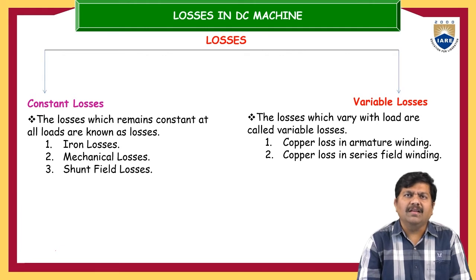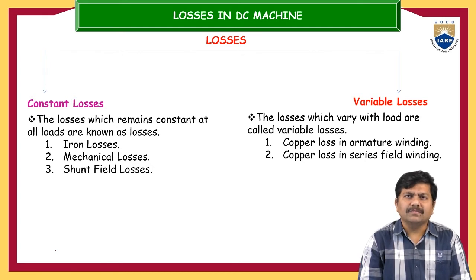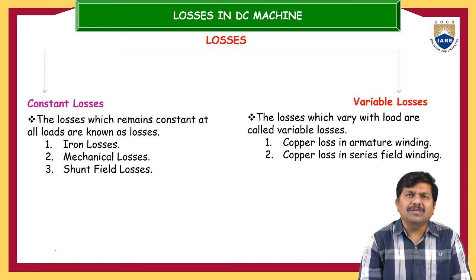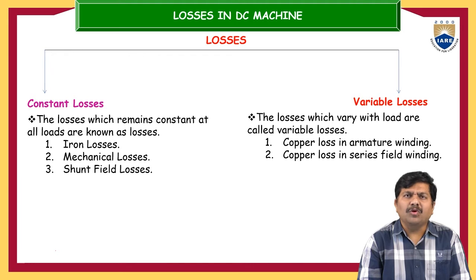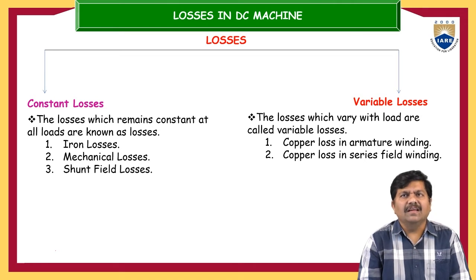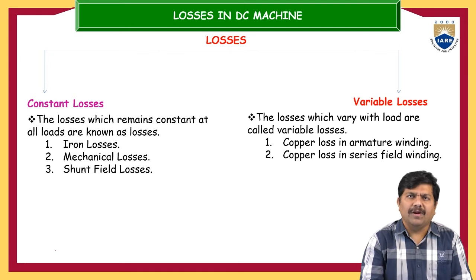Examples of constant losses are iron losses — also called magnetic losses — which are nothing but hysteresis and eddy current losses. The next is mechanical losses, which occur because of friction among mechanical parts or friction between air and mechanical parts. If the rotating armature creates relative motion with air, that air creates frictional forces, and to overcome air friction or windage losses the motor spends extra energy. Mechanical losses are classified into air friction and windage losses. One more loss is the shunt field copper loss.